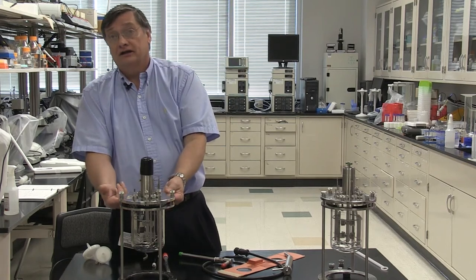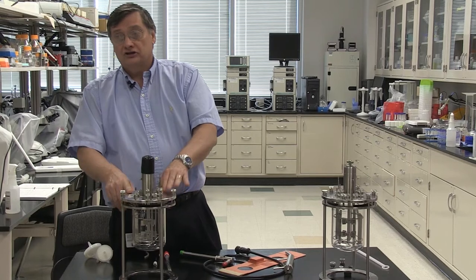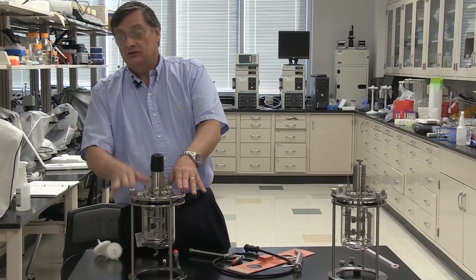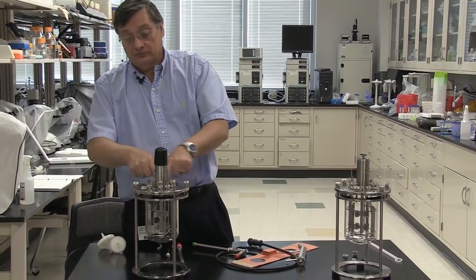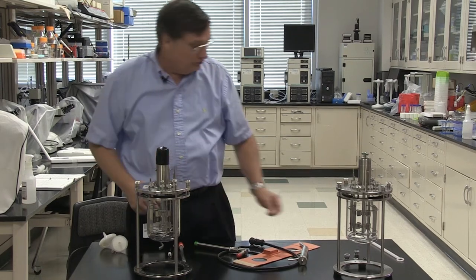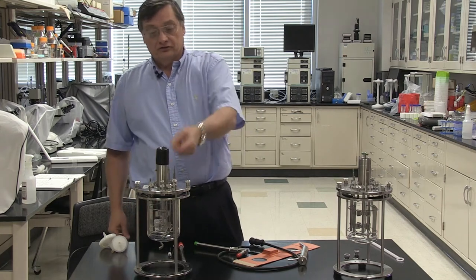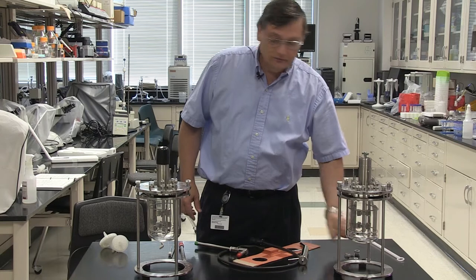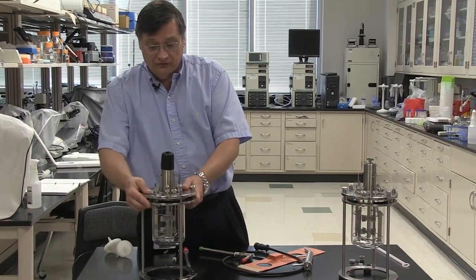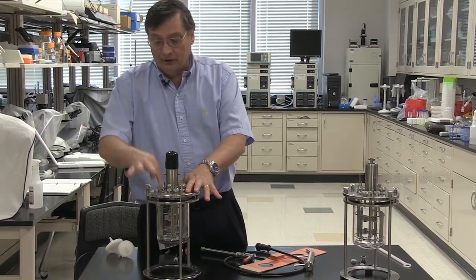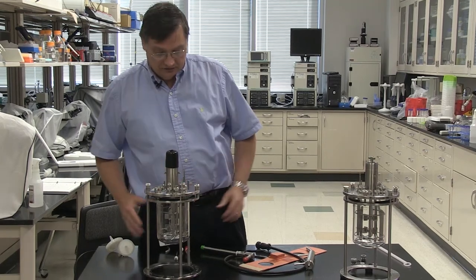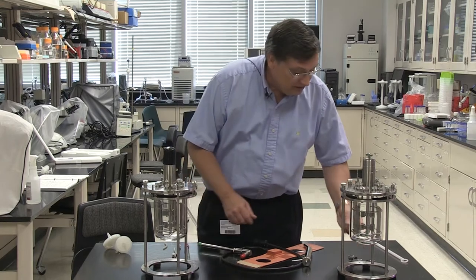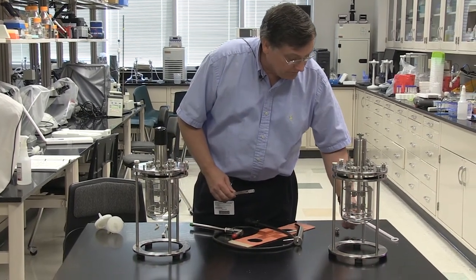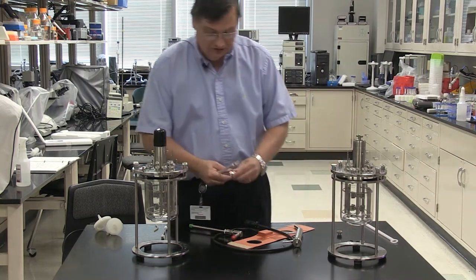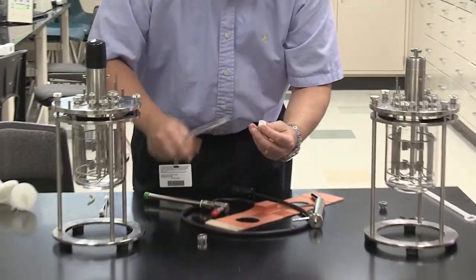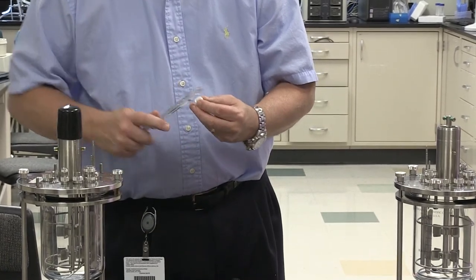One thing I should have pointed out. Earlier I showed you the O-ring that was on the bottom of that. It's a good practice to use some silicone lubricant, which is kind of a grease, on all the rubber fittings, both the O-ring that goes on the base of the head plate and also the little small rubber O-rings that are going to fit down at the bottom of all the fittings. Okay, so we've got the head plate in place. The triports kind of live there. And so now we have the things that are going to add to the top. Now I've already gone over how these triport or these multi-piece fittings work. So we have to assemble those. Oops.